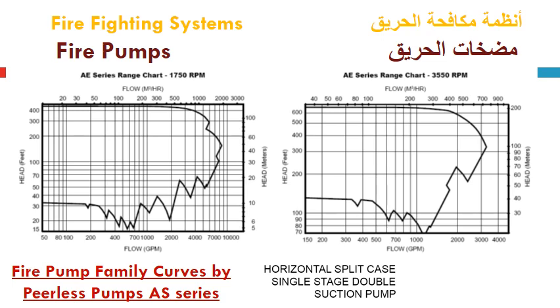It should be clear that for all fire pumps we use one pair of pole motor at high speed. So in fire pumps we use this set of family curves, and this set of curves we don't use for fire pumps, but we can use it for irrigation or HVAC chilled water pumps or hot water pumps. So in fire we always use this high speed using one pair of pole motor at 50 Hz, which gives us 2950 RPM.